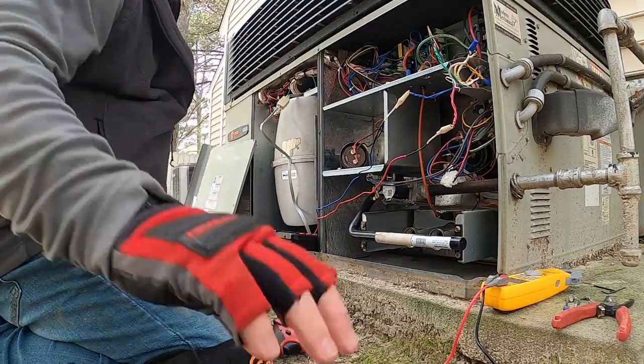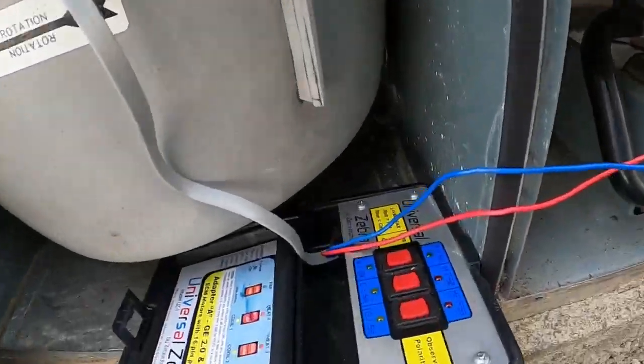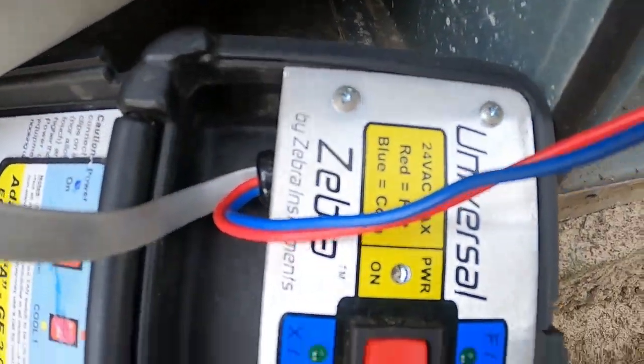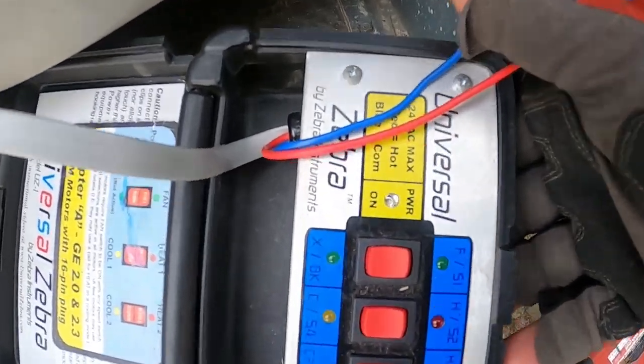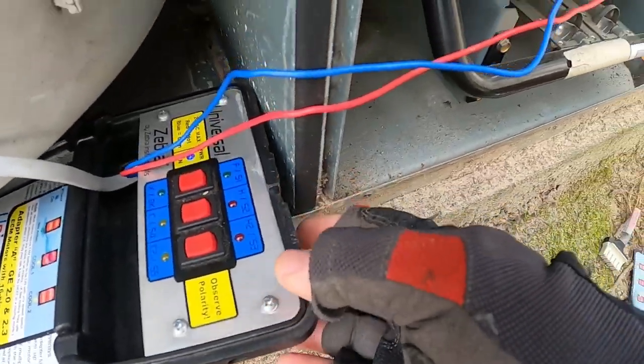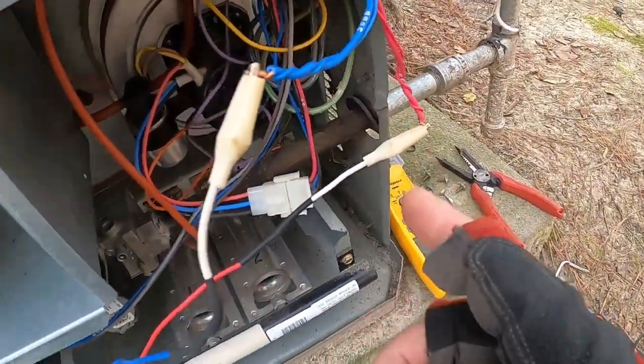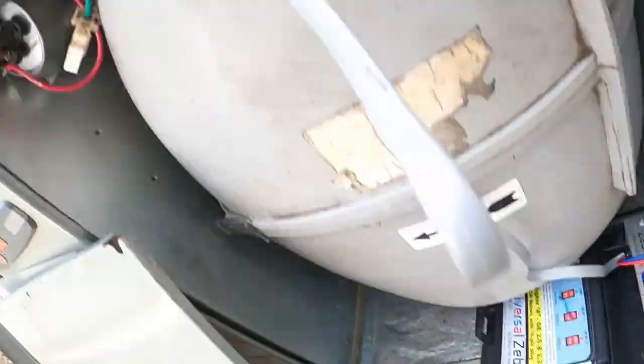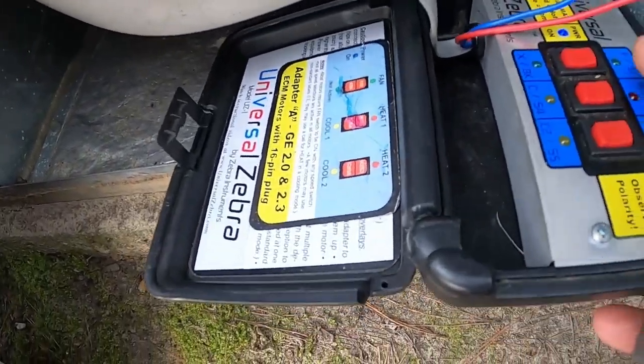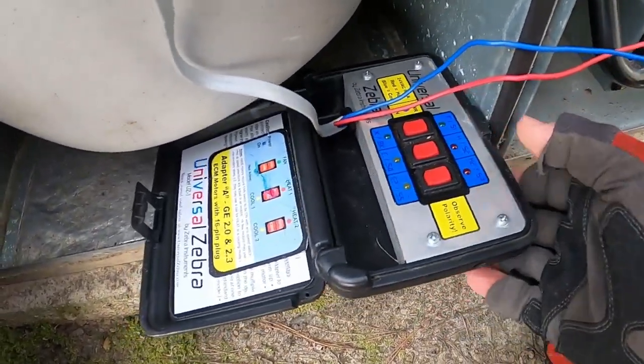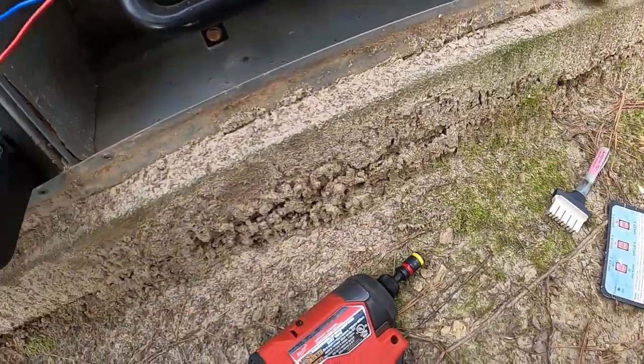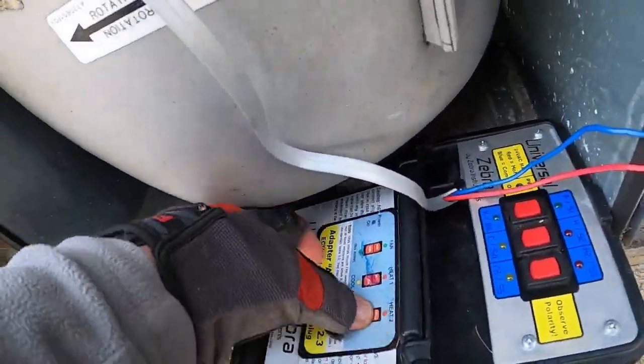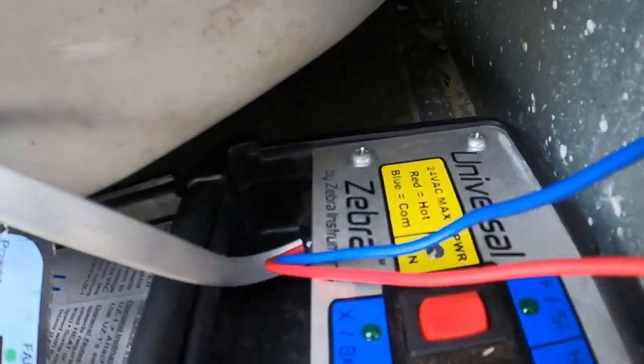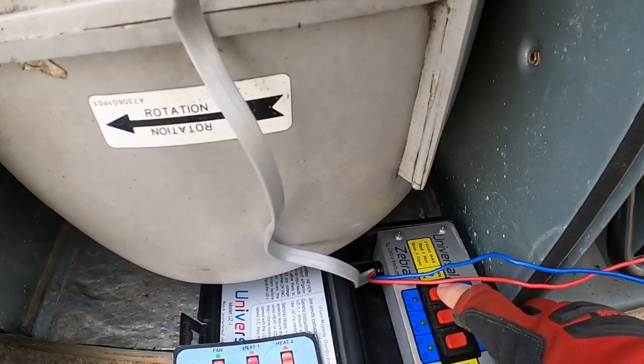Alright guys, so I've got this tester hooked up. We have a blue light. I don't know if that shows on the video or not. Sometimes it does, sometimes it doesn't. But we've got our power here. Basically you just connect your 24 volt hot and common, and then you connect this to your motor with whatever adapter you need, and then we'll try to run this thing and see what it does. Where's the one for this motor? It's going to be this one right here. And let's turn the fan on, see what happens.